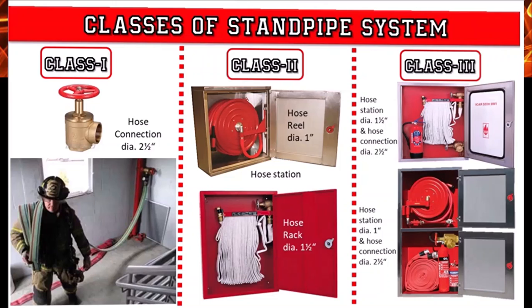For the Class 2 system, it features permanently installed hoses on pin racks or reels that can be accessed by anyone in the event of a fire. They feature 1.5 inch hose connections and are often located in hallways of buildings. Because hoses are sometimes poorly maintained and building owners are concerned about liability if an untrained individual gets hurt trying to fight a fire, these systems have fallen out of favor and are typically present in older buildings.